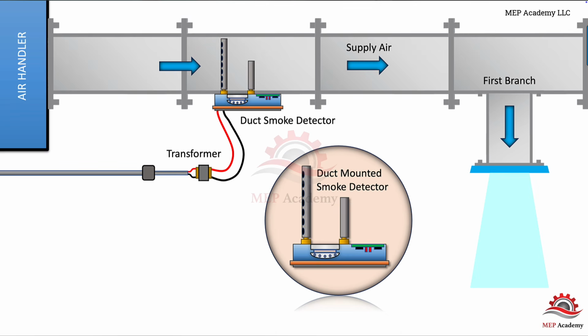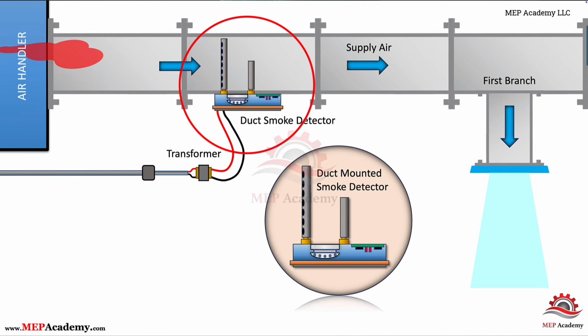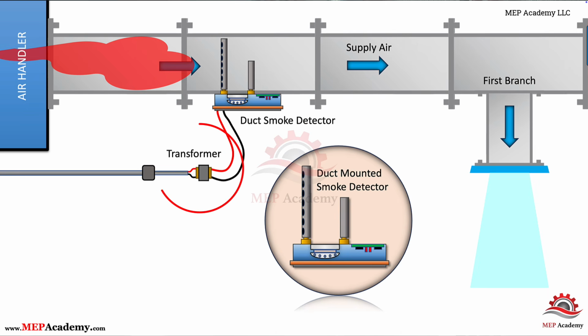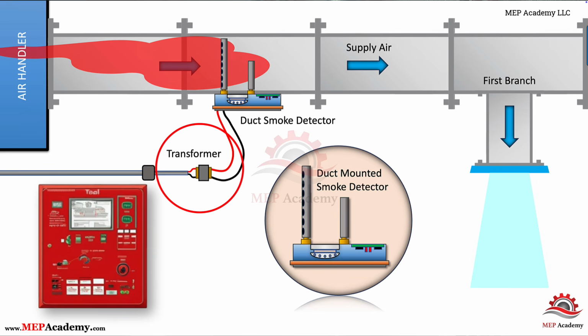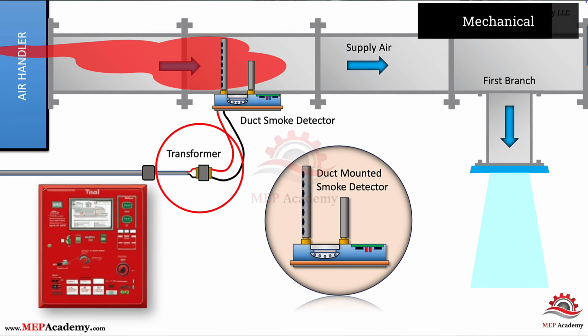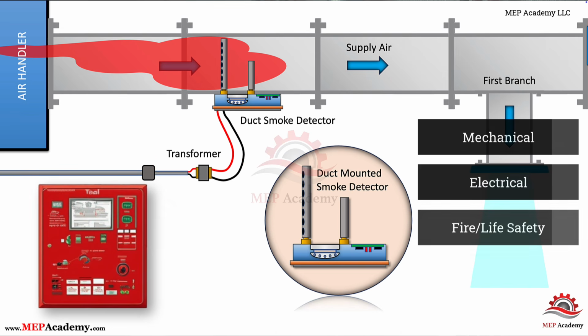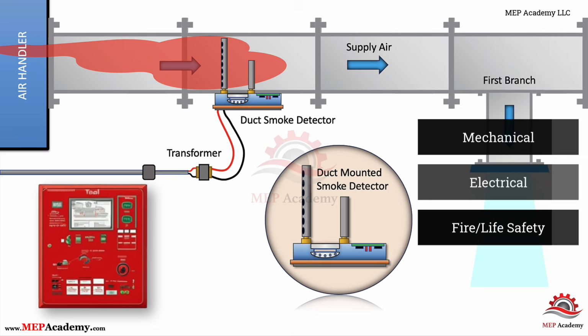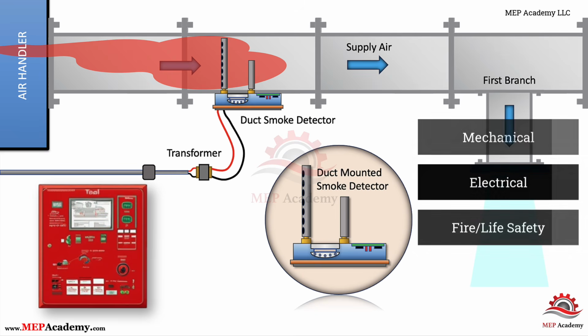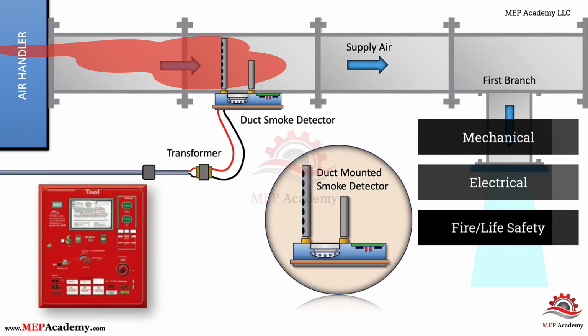The first and most common issue involves duct-mounted smoke detectors. Duct smoke detectors are physically installed in the ductwork, so they are often assumed to belong to the mechanical contractor. However, these devices require electrical power and must interface with the fire alarm system to shut down air handling equipment during a smoke event. Because 3 systems are involved, mechanical, electrical, and fire alarm, responsibility is frequently unclear. Mechanical drawings typically show the detector location, while electrical drawings may only show general power distribution. Fire alarm drawings may show monitoring points, but not the wiring path.